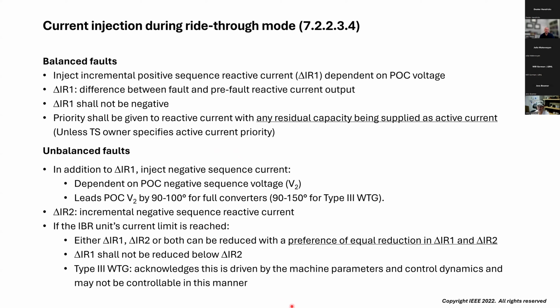For unbalanced faults, now we have a deviation in positive sequence voltage as well as negative sequence voltage. So now we want to inject an incremental reactive current in the negative sequence that needs to lead the POC voltage. So it's going to be working to reduce the negative sequence voltage at the POC.